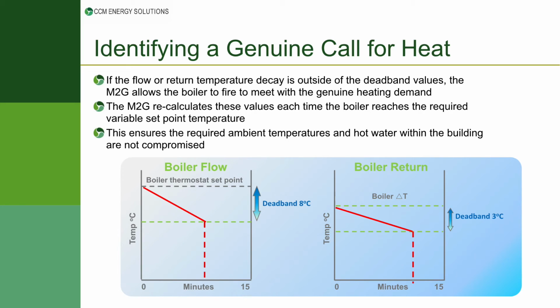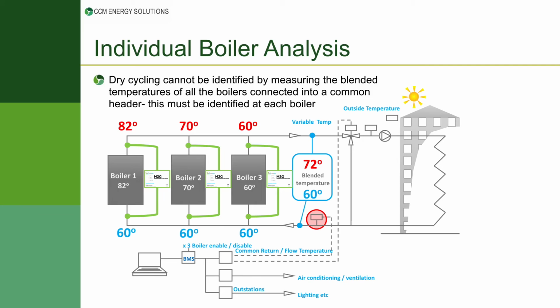As I say, it's identifying a genuine call for heat. And it also measures your individual boilers. Your BMS will be measuring a common header temperature and a common return temperature. That doesn't look at your individual boilers. It looks on a macro level, whereas we want to be looking on a micro level.